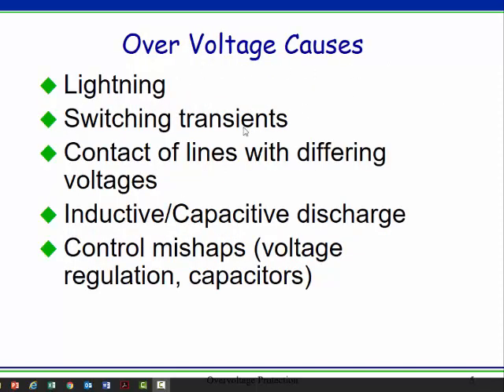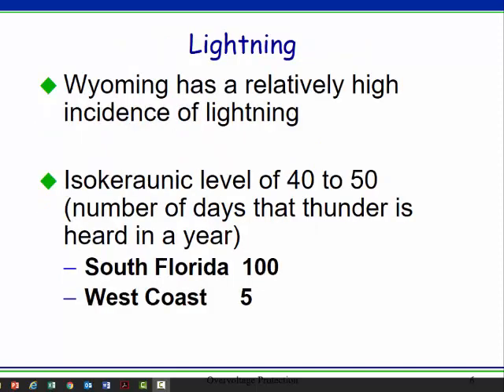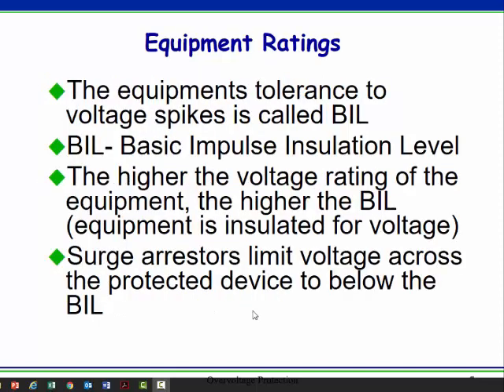What causes overvoltage? Well, lots of things. We tend to think of lightning, but there are other causes. I've seen large transmission lines fall on small distribution lines, and suddenly a 20,000-volt line is energized at 138,000 volts — that sort of thing. Here in Wyoming, we have a fairly high isokeraunic level. Florida is very high. The West Coast is very low.